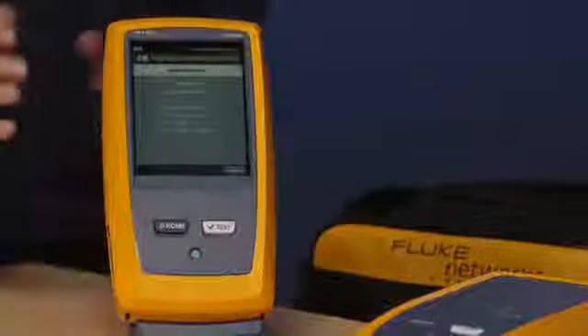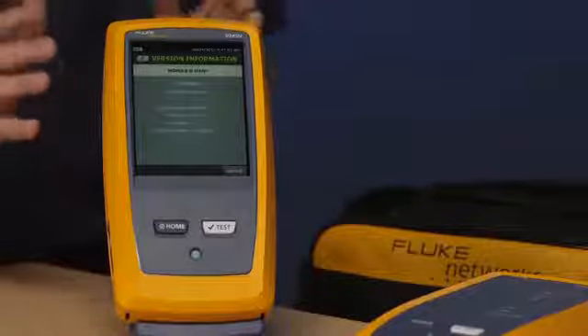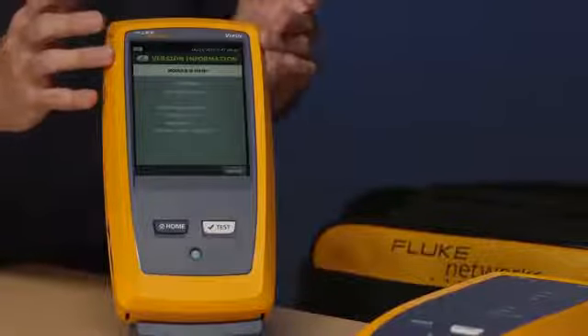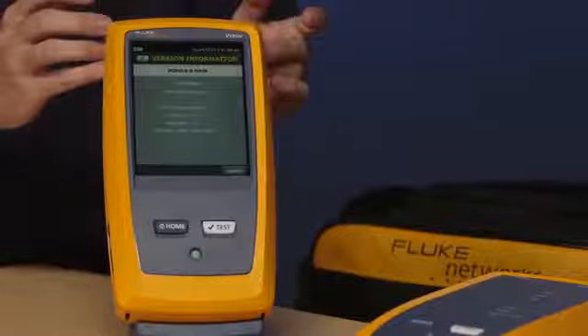So go ahead and tap module for me. So now we see the calibration date. Remember, the mainframe is just the operating platform. The measurement system is the module itself. The calibration is required every 12 months, and that calibration date will be stored on your test report and can be reviewed by your customer.